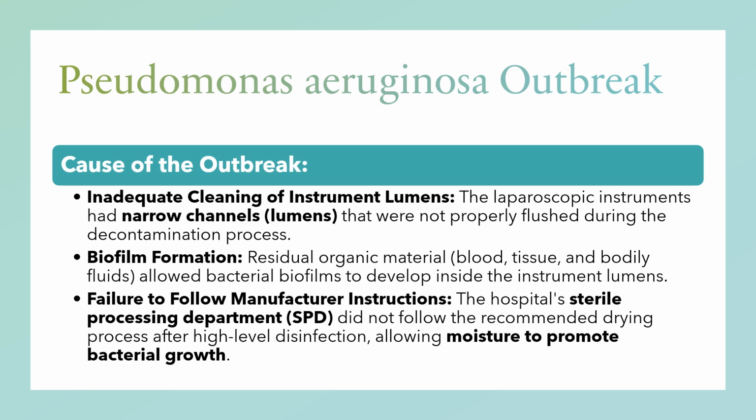Biofilm was allowed to develop inside the instrument lumens because they were not properly being flushed and cleaned out. The hospital also was not following the manufacturer's instructions for use. There's a specific drying time that was not being adhered to, which means that moisture was allowing that bacteria to continue to grow, as well as the biofilm.